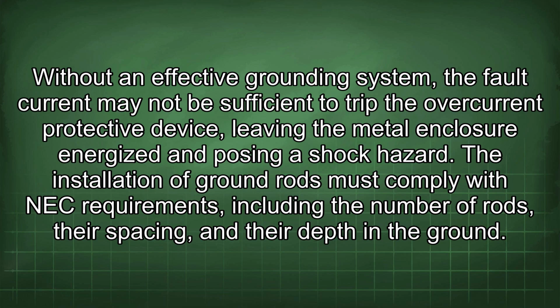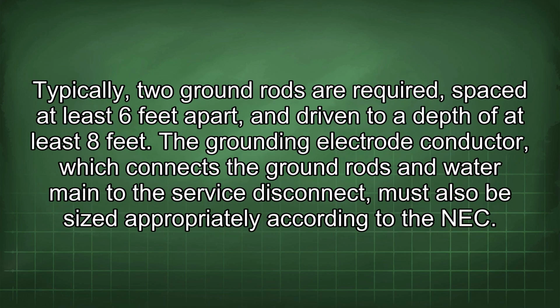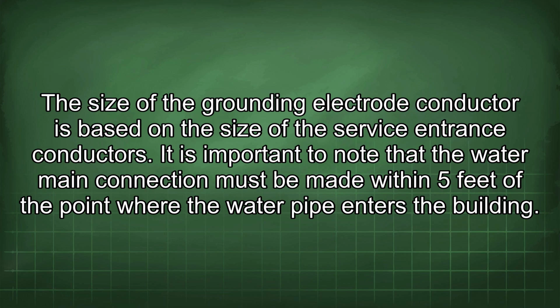The installation of ground rods must comply with NEC requirements, including the number of rods, their spacing, and their depth in the ground. Typically, 2 ground rods are required, spaced at least 6 feet apart and driven to a depth of at least 8 feet. The grounding electrode conductor, which connects the ground rods and water main to the service disconnect, must also be sized appropriately according to the NEC. The size of the grounding electrode conductor is based on the size of the service entrance conductors. It is important to note that the water main connection must be made within 5 feet of the point where the water pipe enters the building.